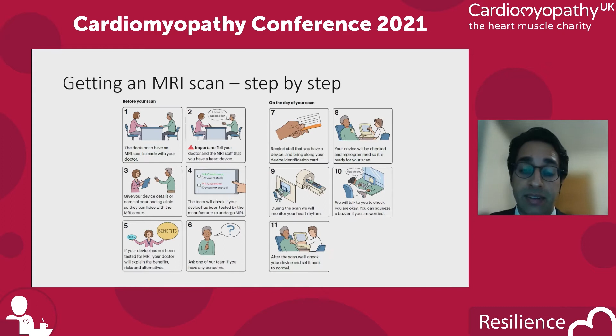And we've said it's important to check the details of the device. And that's because there are different types. The more modern pacemakers are now tested to undergo MRI scanning. And this was an industry initiative from about 2008. And it's because the industry recognized that patients weren't getting access to the same healthcare as everyone else. And so they designed modern MRI conditional pacemakers to undergo MRI. And so they designed the leads from the bottom up, really, from designing the ferromagnetic components to extra shielding for the computer systems, changing the switches within the device as well so they don't respond to a magnet.